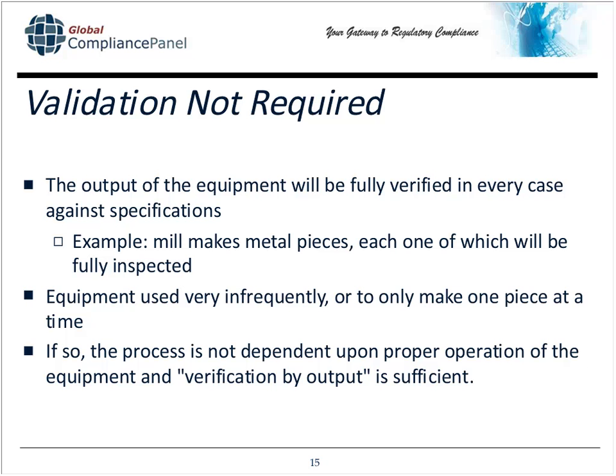Another example of times when validation isn't required is if you have a piece of equipment that's used very infrequently, or maybe you only make one piece at a time. If you use equipment to make an operating table, for example, this equipment is used relatively infrequently. It's used all the time, but you only make one piece per, let's say, week. If so, you can do verification by output, and you explain how you're verifying that piece of equipment, whether it's fully verified or it's infrequent.